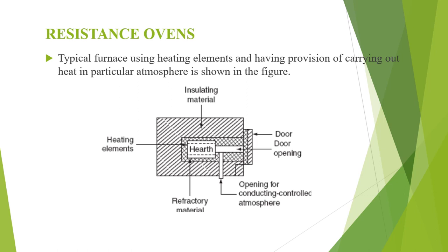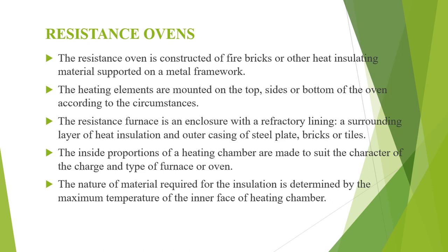Furnaces operating at low temperature are called resistance ovens. The resistance oven is constructed of firebricks or other heat insulating material supported on a metal framework. The heating elements are mounted on the top, sides or bottom of the oven according to the circumstance. The resistance furnace is an enclosure with refractory lining, a surrounding layer of heat insulation and outer casing of steel plate, bricks or tiles. The inside of the heating chamber is made to suit the character of the charge and type of furnace or oven. The insulation material required is determined by the maximum temperature of the inner face of the heating chamber.